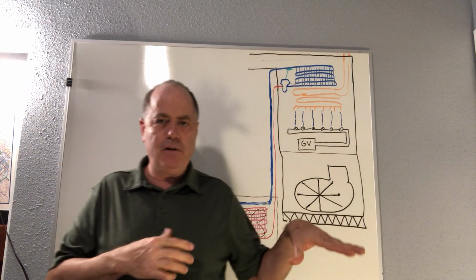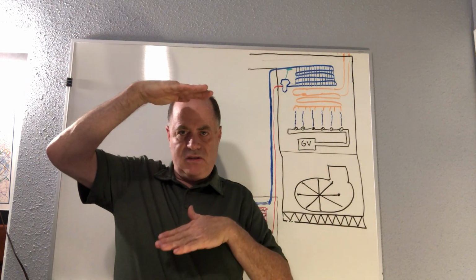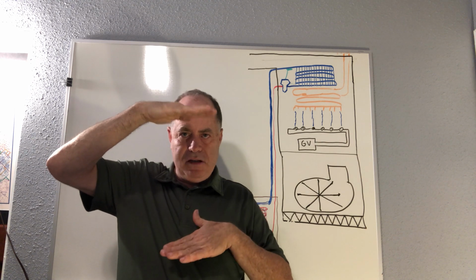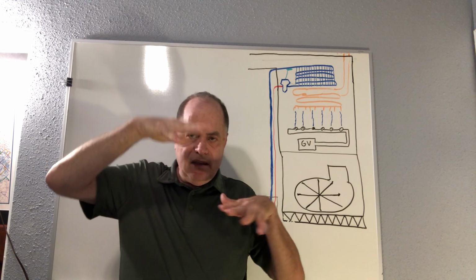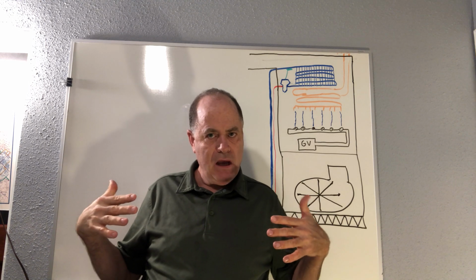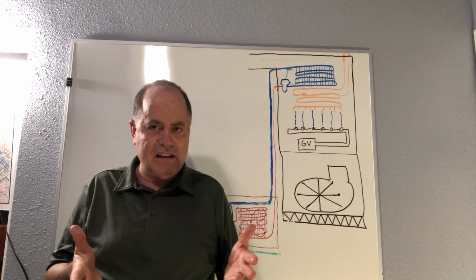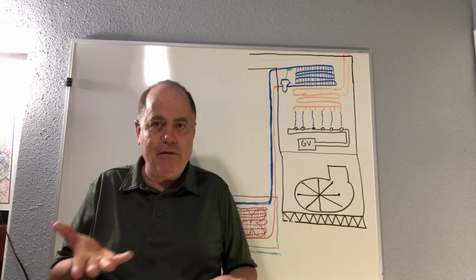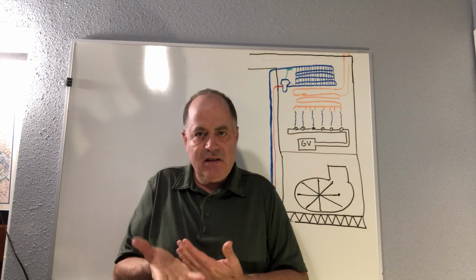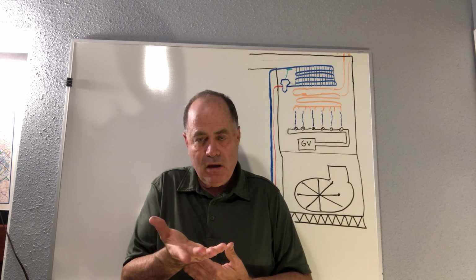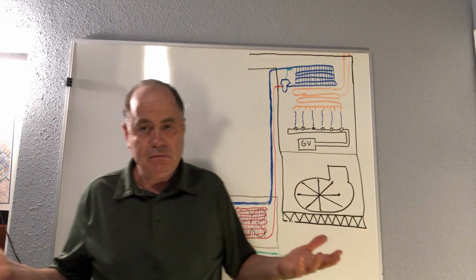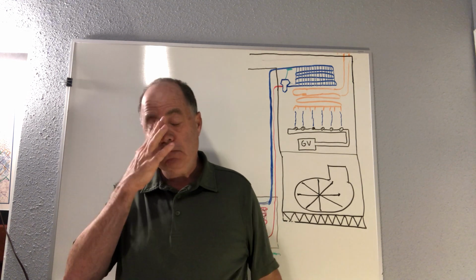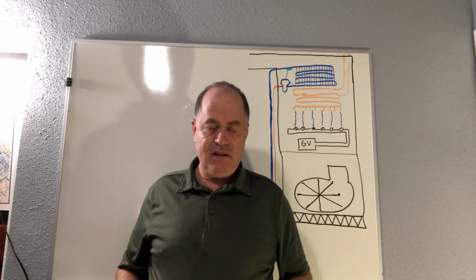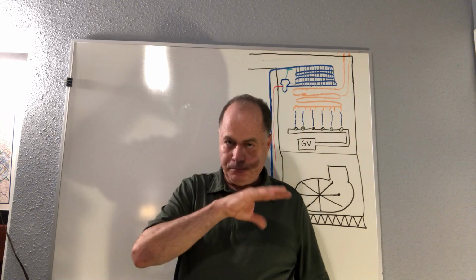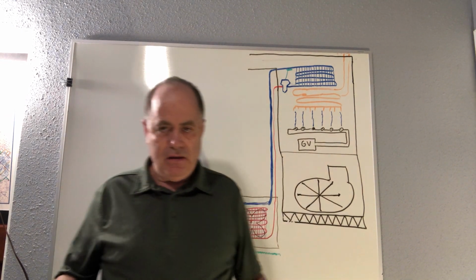These are like old furnaces in houses that are only about this high sitting on the floor, and maybe there'll be a little piece about this high in the back, and then it's usually a raised foundation, and most of the furnace that operates the gas valve and everything is actually below the floor level and sticks under your house in that raised foundation. And so we don't want a flood to come and get in your heater when you really need it. So it's got to be off the ground 6 inches generally, unless it's a special design with a sealed chamber, then they only make it 2 inches off the ground. Okay?